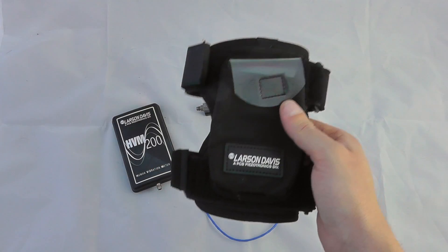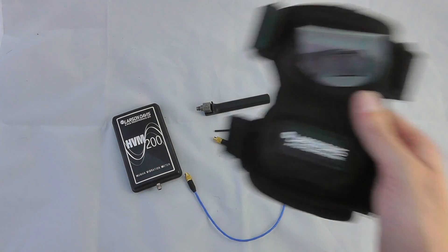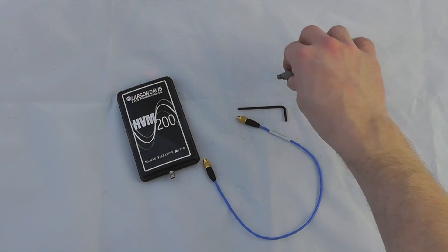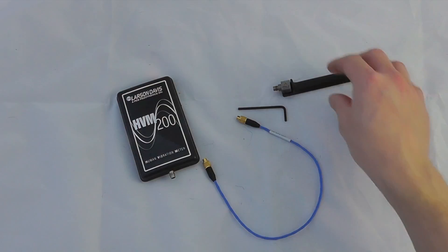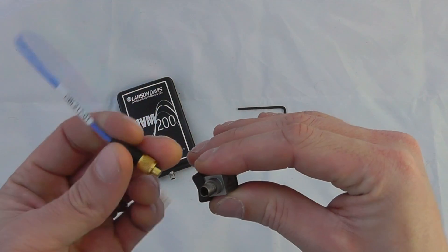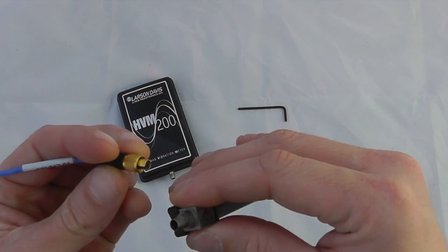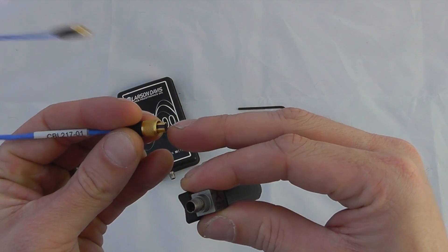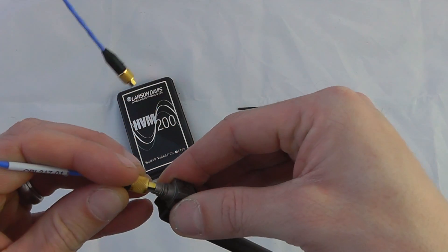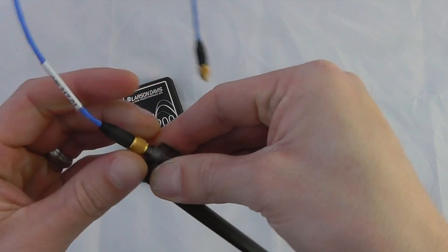Now to attach the accelerometer to the instrument, we can take the accelerometer. There is a notch on the side of the accelerometer which will line up with a black notch on the side of the cable.